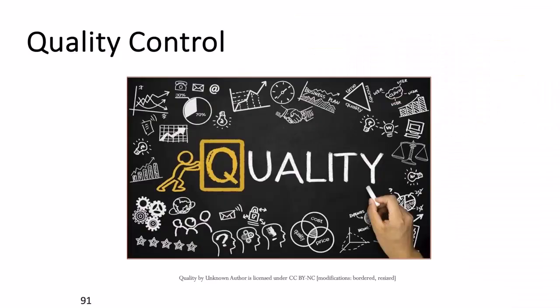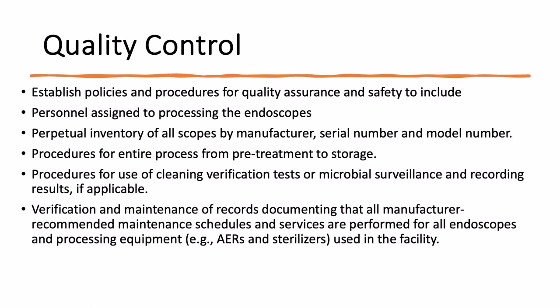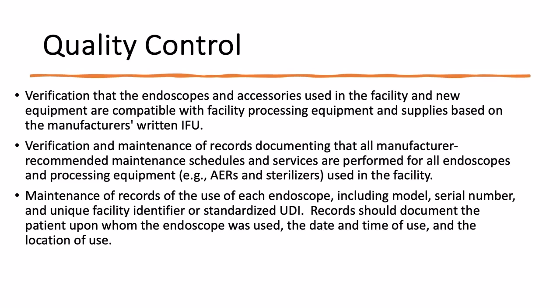Quality control. You need a quality control program, and all the things we talked about should be included. Who's assigned to processing, your inventory of all of your scopes. That is required, a perpetual inventory. Procedures for the entire process. Procedures for cleaning verification tests or microbial surveillance. Verification of maintenance records documenting that all manufacturers' recommended maintenance schedules are being performed for endoscopes and equipment. Verification that the scopes and accessories used in the facility and new equipment are compatible with your processing equipment and supplies. Verification and maintenance of records documenting that all recommended schedules and services for scopes are being used.